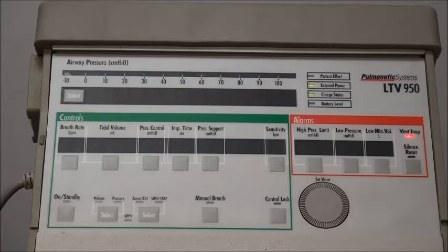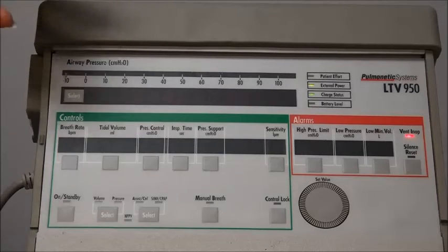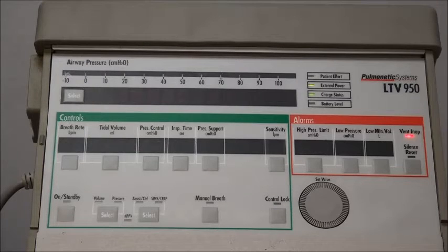Now, some things that can cause that would be some sort of obstruction in your tubing. It could be water in your tubing. It could be that your patient needs to be suctioned. Sometimes if your patient is coughing or talking, you can get a high pressure alarm. That's something to do with your patient or your circuit. It's nothing to do with anything wrong with the ventilator. It's just alerting you that for some reason your patient's pressure is going higher. And if the patient's coughing or needs to be suctioned, that's something you can easily take care of.